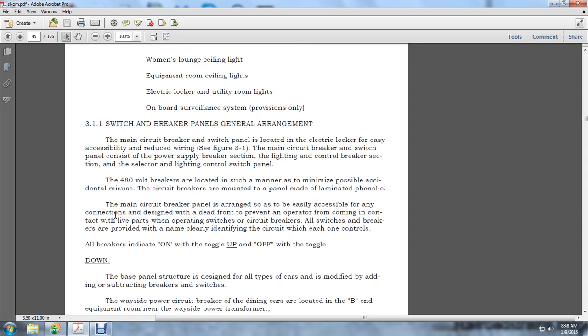The circuit breaker is mounted in the panel made of laminated phenolic. The main circuit breaker is arranged so it is easily accessible. A dead front prevents the operator from coming into contact with live parts of the operating switches and the circuit breakers. All switch breakers are provided with a name clearly identifying the circuit which each one controls. All breakers indicate on with the toggle up and off with the toggle down.